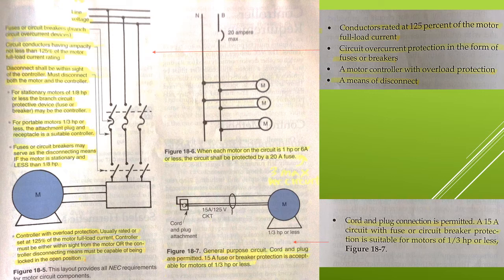General purpose circuit guide. Follow these general guidelines. First, when each motor is 1 horsepower or 6 amps or less, this circuit will require a 20 amp, 125 volt or smaller fuse or breaker, or a 10 amp, 250 volt. For this, see figure 18-6, which is on the middle of the screen top.